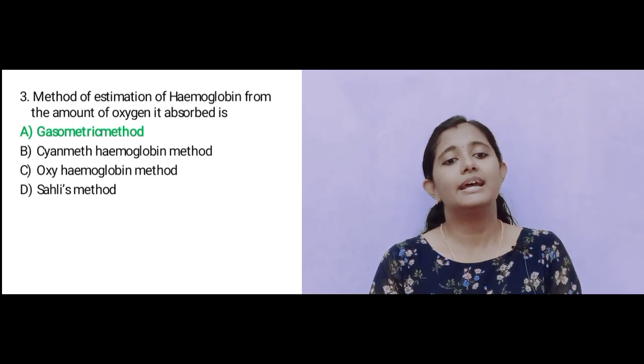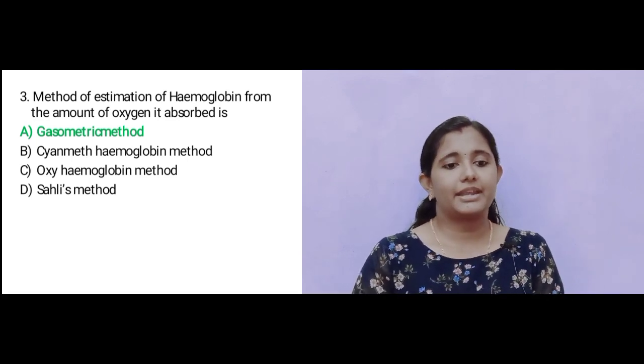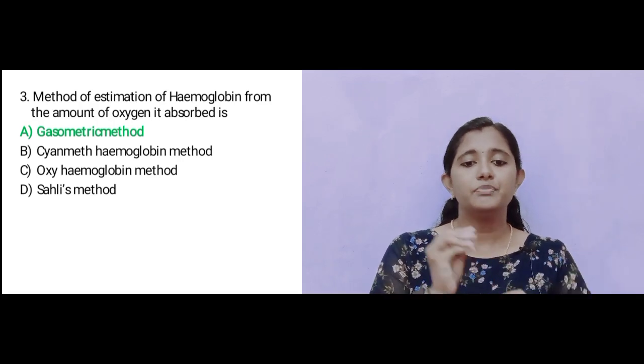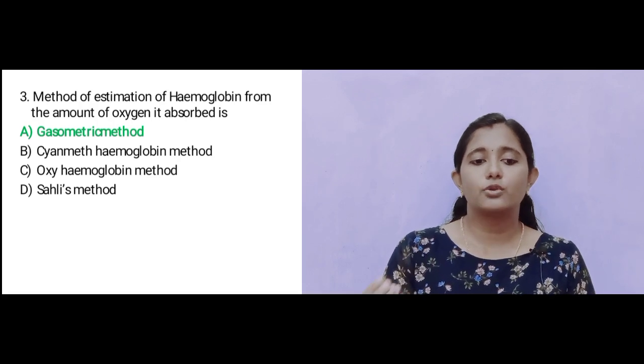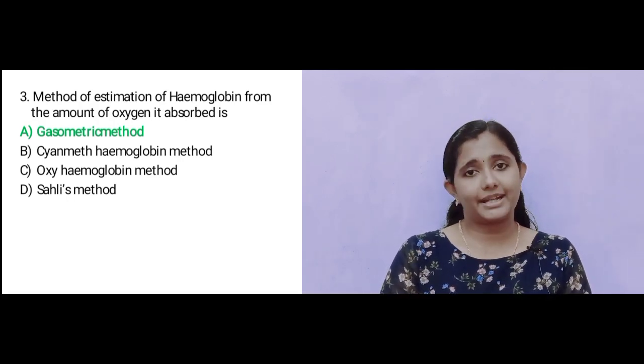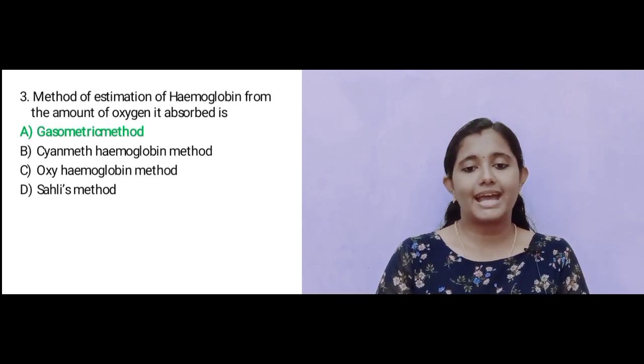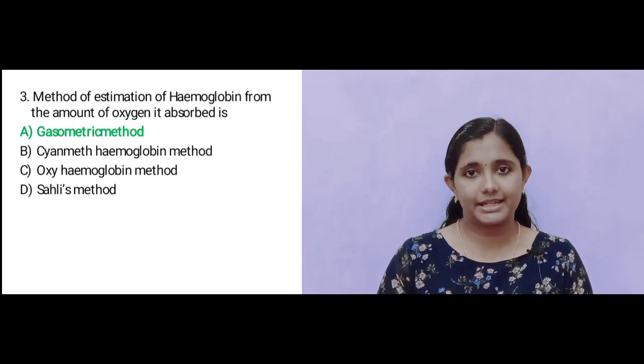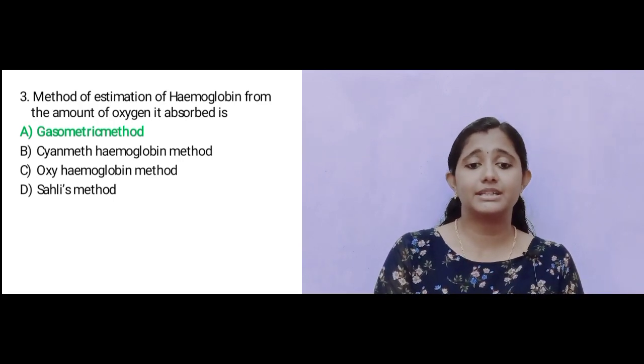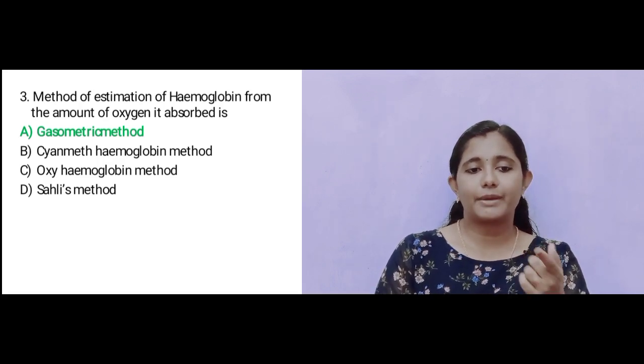The gasometric method estimates hemoglobin by measuring oxygen-carrying capacity — oxygen is absorbed and measured. In the cyanmethemoglobin method, potassium ferricyanide solution converts hemoglobin to methemoglobin, which is then detected. In Sahli's method, hydrochloric acid converts hemoglobin to acid hematin, read using a comparator as a colorimetric method.